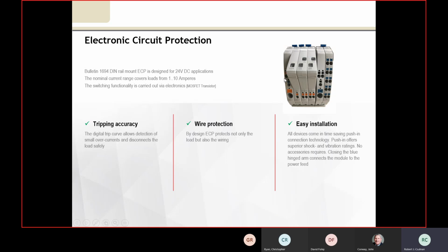Many times the question is, is there an adjustable version? In this situation there isn't, and the reason is we don't want the end customer to be able to go in and increase the current on the unit and essentially override its function. So in this case, they're fixed. In the future, we'll have the ability, with IO-Link connected to this, to have an adjustable unit. The idea behind IO-Link is that only the designer and the programmer will be able to change that, and somebody on the floor with a screwdriver won't be able to just increase the current if they're getting trips, because obviously that's not the right way to run the system. So an electronic fuse is another way of wiring your system.